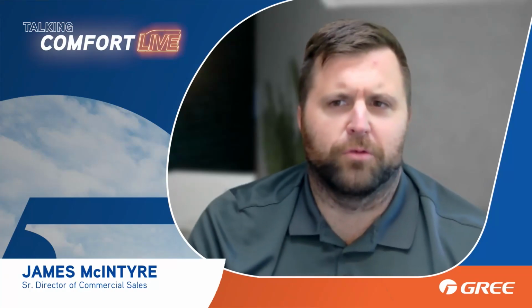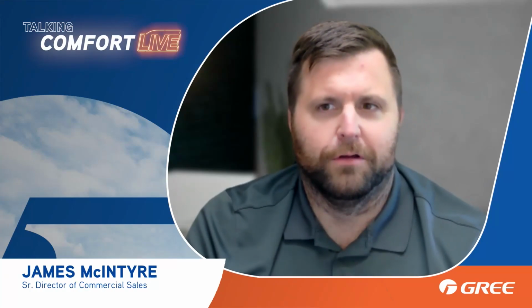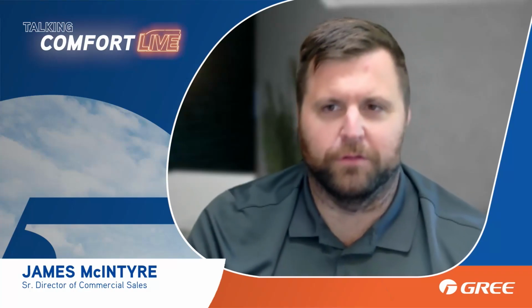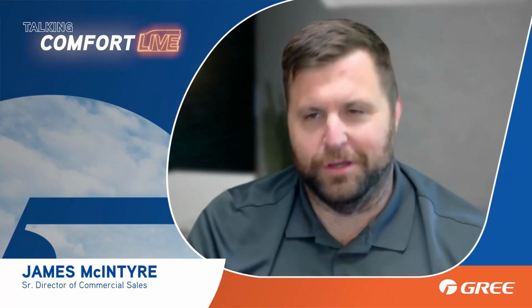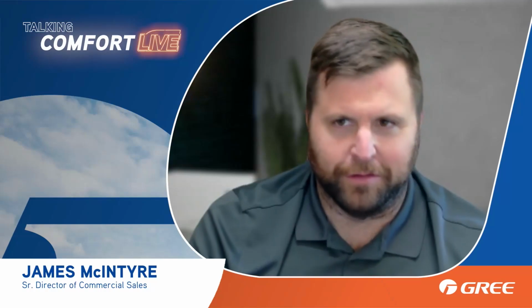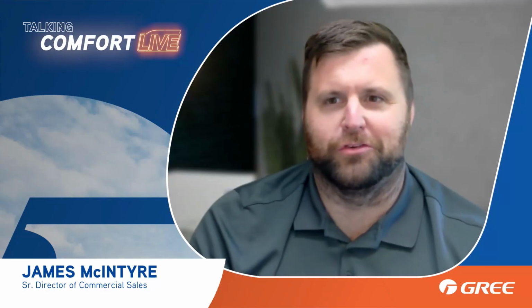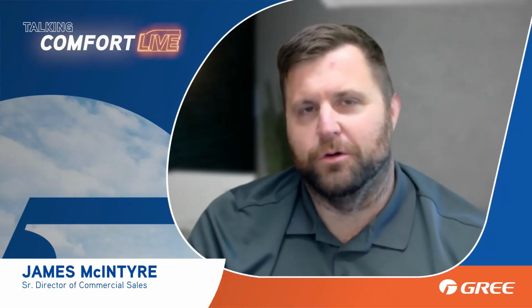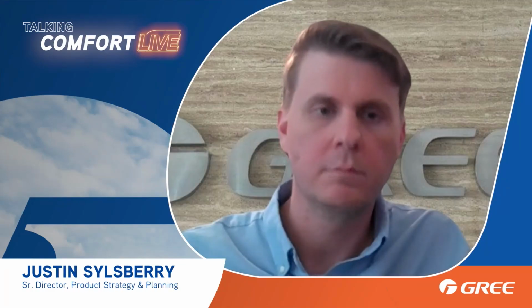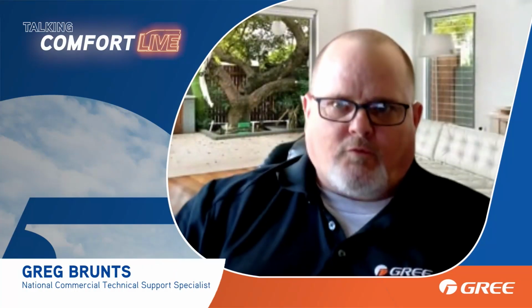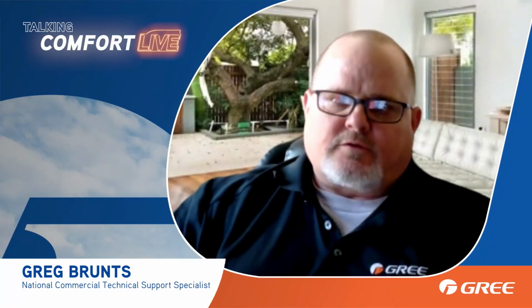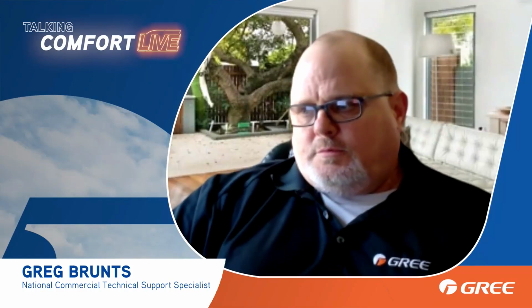In our case, what that looks like is it just doesn't ramp up like I want it to. Well, the reason it's not going to ramp up like you want it to is because it's too cold, to prevent that ice from building up and the liquid flowing back and the oil washing out and all that. And the bottom line is it's going to end up on an error code, not with a failed compressor. Right. So it's not going to let you get away with poor ductwork or over filtering and all these other things, right? Right. Exactly.